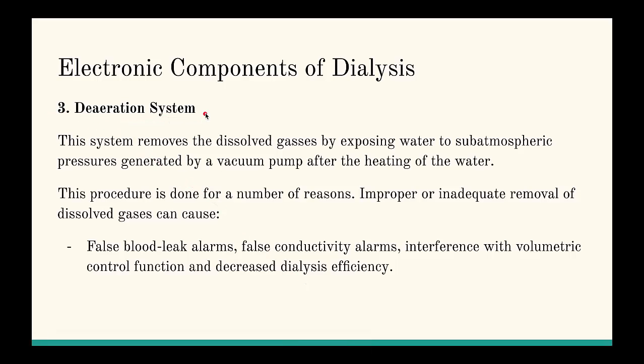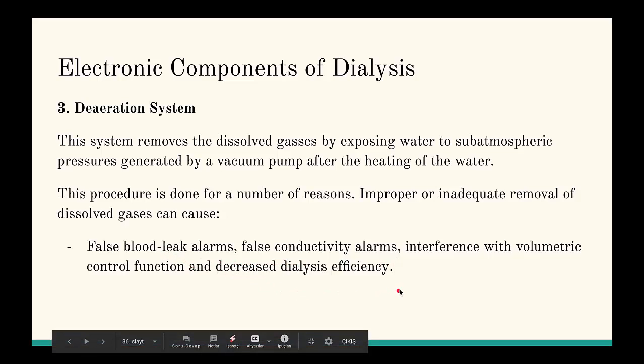What the system does is it removes the dissolved gases by exposing water to the subatmospheric pressures generated by a vacuum pump after the heating of the water. This procedure is done for a number of reasons. Improper or inadequate removal of dissolved gases can cause many different problems. They can cause false blood leak alarms, false conductivity alarms, interference with volumetric control function, and decreased dialysis efficiency.